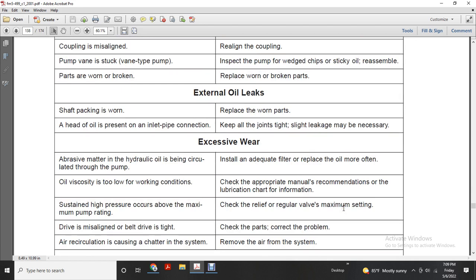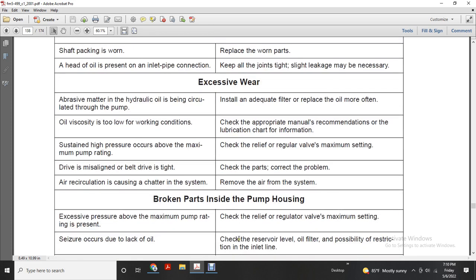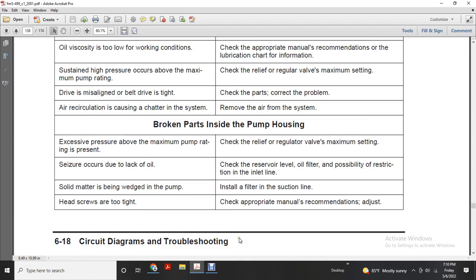Excessive wear: abrasive matter in the hydraulic oil may be circulating through the pump. Install an adequate filter and replace the oil more often. Oil viscosity too low for the working condition: check the appropriate lubrication chart for the information. Sustained high pressure exceeds the maximum pump rating: check the relief and regulator valve maximum setting. Drive misaligned or belt drive is too tight: check the parts and correct the problem. Recirculating causes chattering in the system: remove air from the system. Broken parts inside the pump housing.